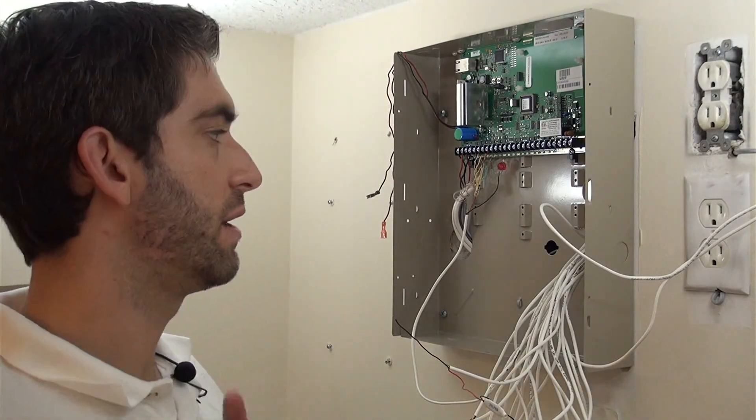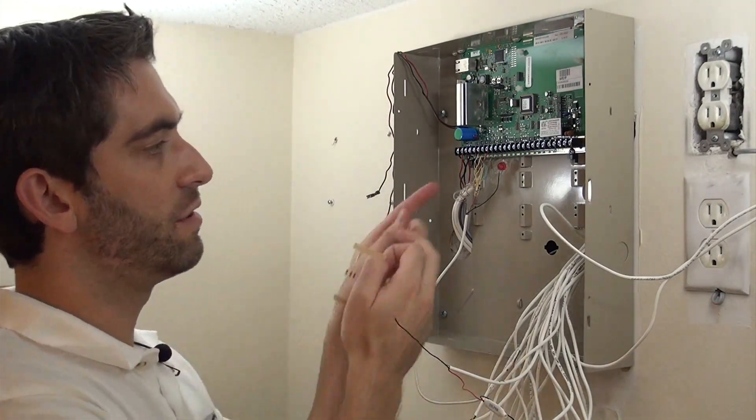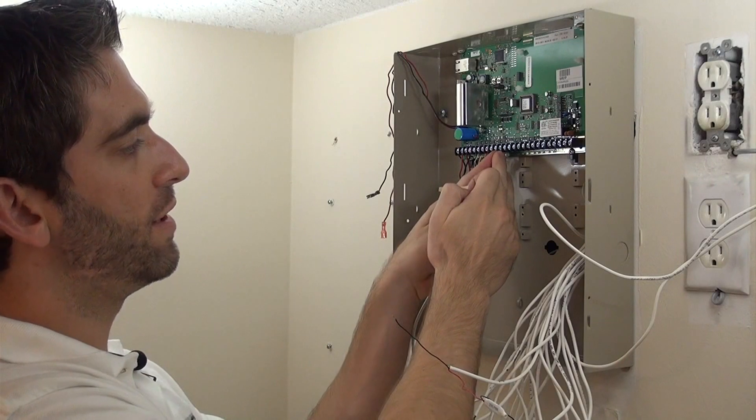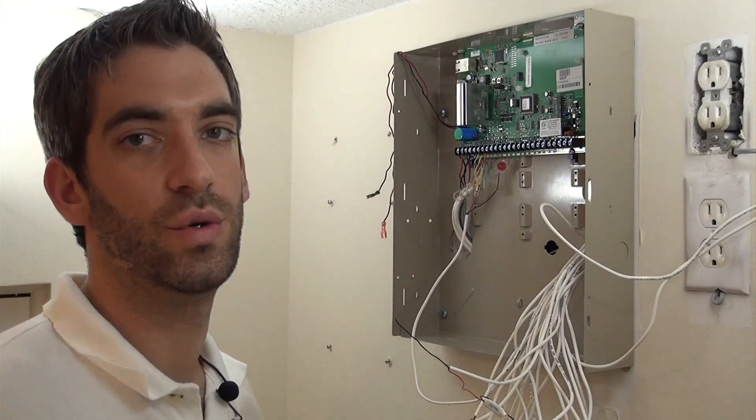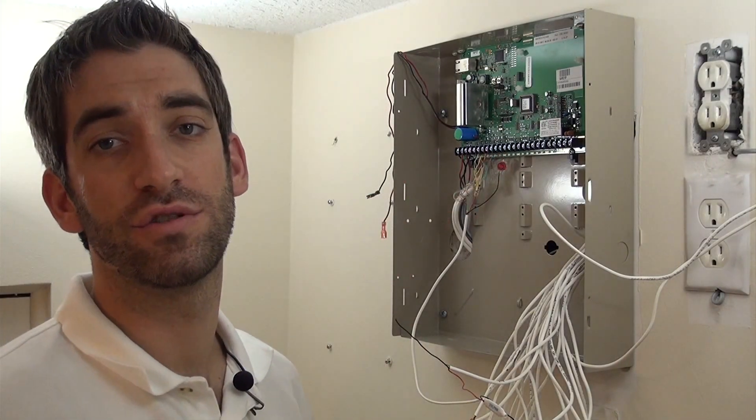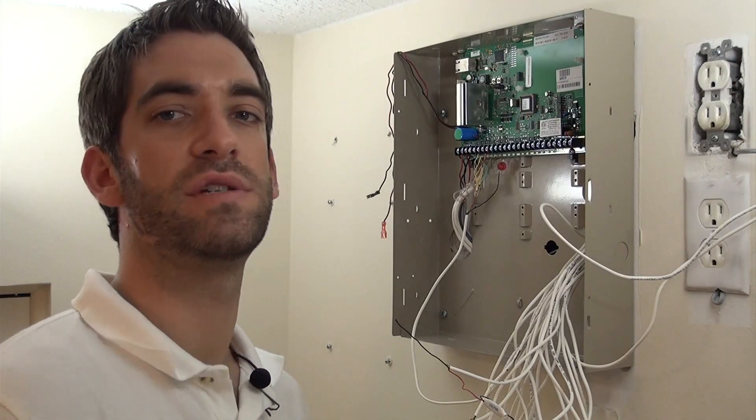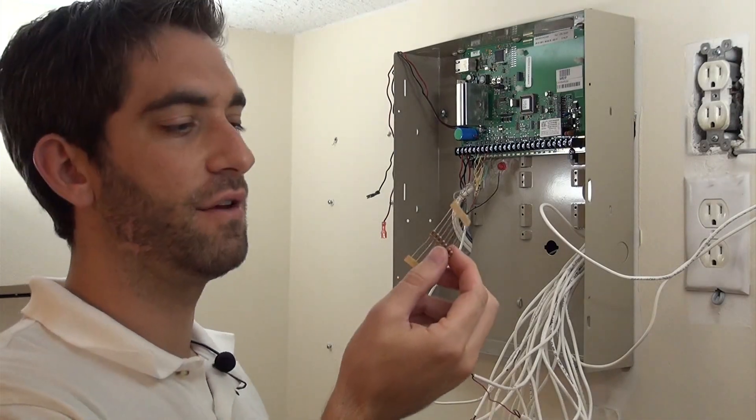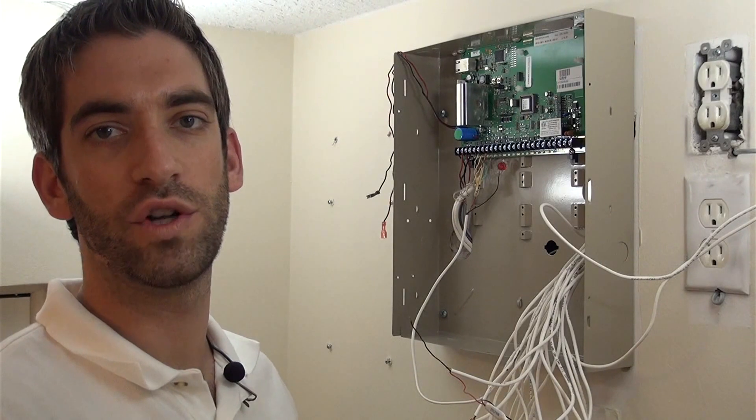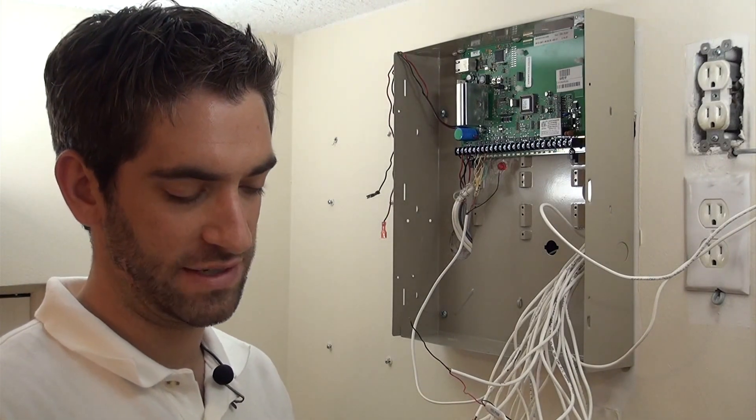So the way you do zone doubling, you're going to take two different zones and land them on one set of terminals, so ground and Z2. And the way it works is your zone 2 will also be your zone 10. And your different value resistor will let you know which device is actually going off.